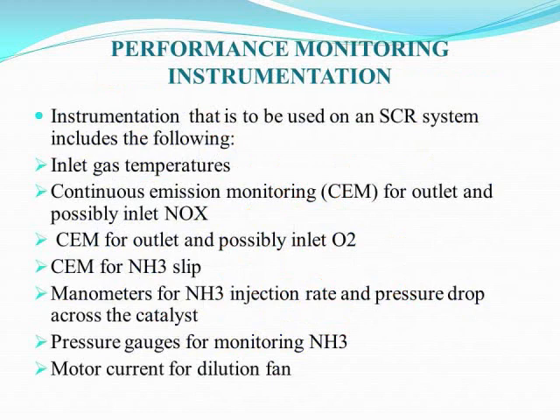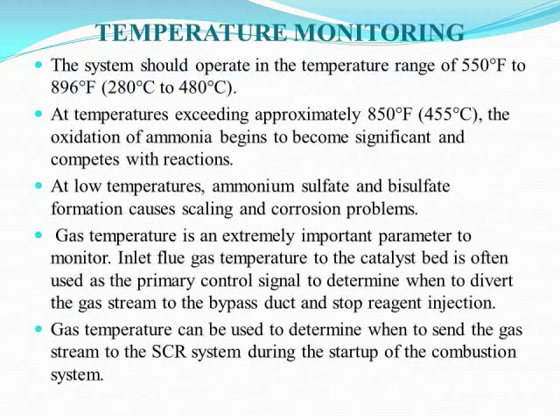Injection is accomplished through a series of injection pipes positioned in a grid formation perpendicular to the flow rate and upstream of the catalyst. This grid layout promotes good mixing of ammonia and flue gas and ensures even distribution across the duct. The temperature at which ammonia should be injected is below 850°F, because above that temperature ammonia will react with available oxygen to produce NOx.